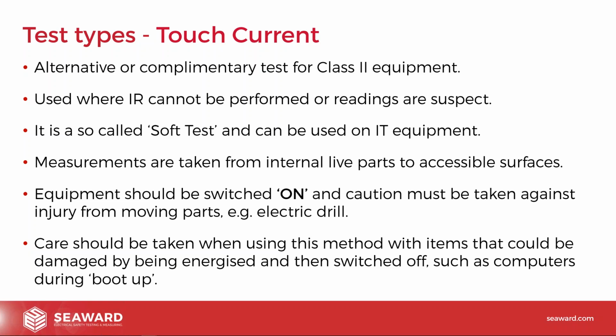We can do it on class 1 if we wanted to, but generally for class 2 equipment, we do a touch current test. Instead of measuring the current coming back down the earth wire, the touch current test measures the current and simulates what would come back through me if I were to touch, for example, a certain screw head. So instead of using my finger, we're using a test probe to touch a certain screw head. And it will measure the test current that would come back down that screw.